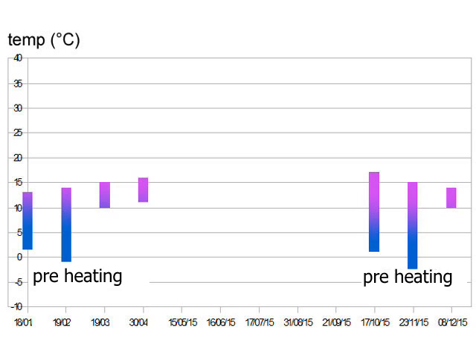The measurements, in blue on the bottom, show the outside air temperatures in winter going up to the top violet measures inside the house. Certain days in winter, the air heats up by 17 degrees — as in November, when the outside air is minus 2 degrees going up to plus 15 after the tube exchange.